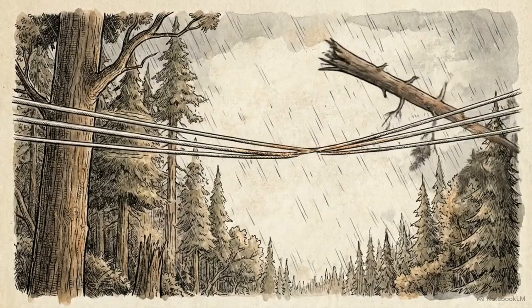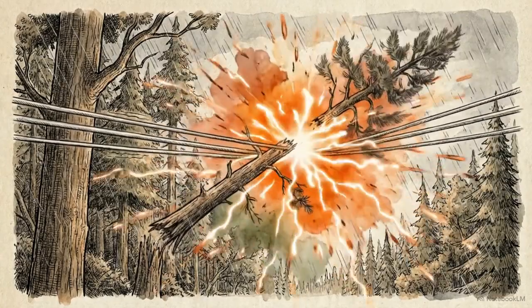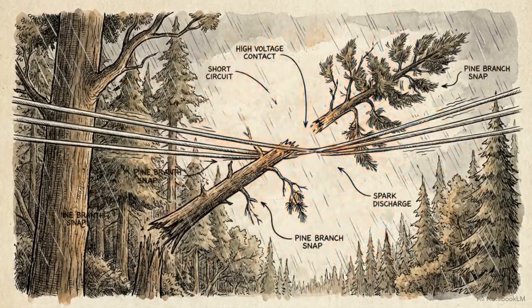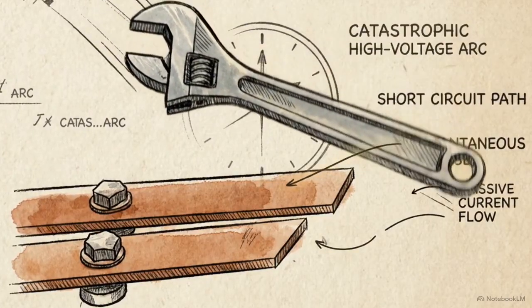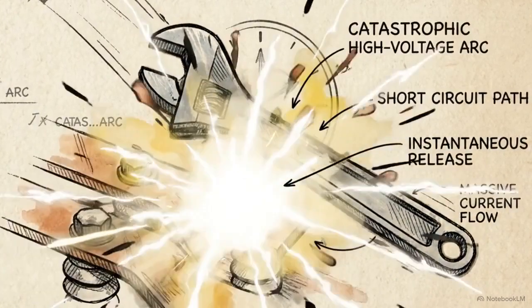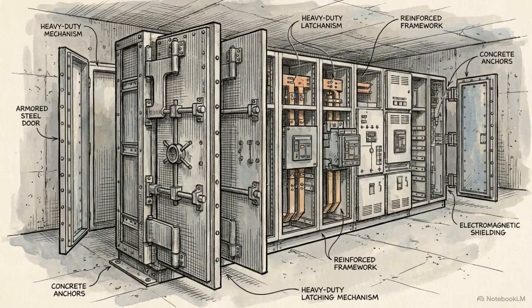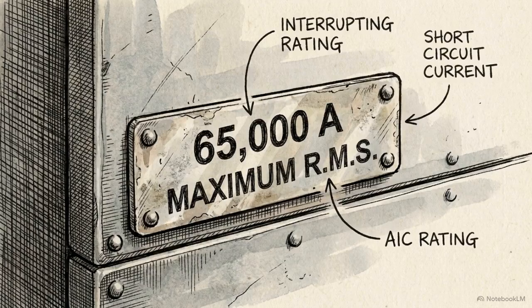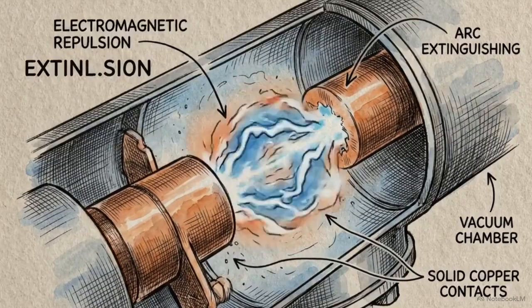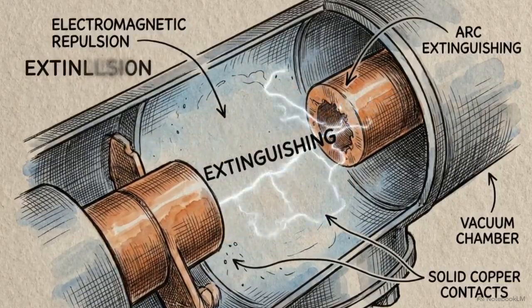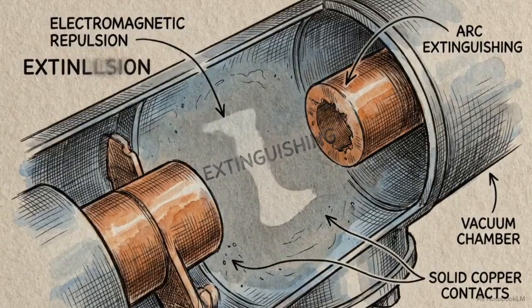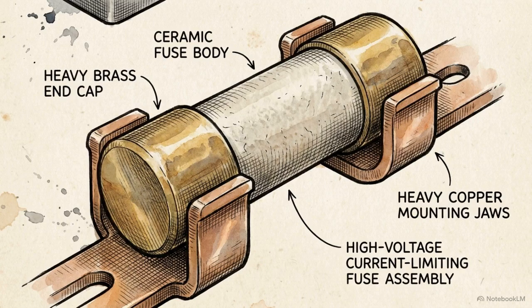broken. The inception angle of a short circuit is entirely random. Whether a tree branch falls across a transmission line or a worker drops a metal wrench across a live busbar, no one controls the exact millisecond the connection is made. Because the timing is a literal lottery, the power grid and its protective switchgear must be preemptively armored to survive the absolute worst-case scenario. Heavy-duty circuit breakers undergo rigorous testing to earn specific interrupting ratings. These ratings prove they can physically separate their contacts and extinguish an electrical arc even under the extreme stress of severe DC offsets. For even faster protection, engineers deploy current-limiting fuses.